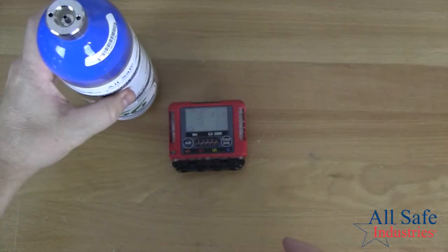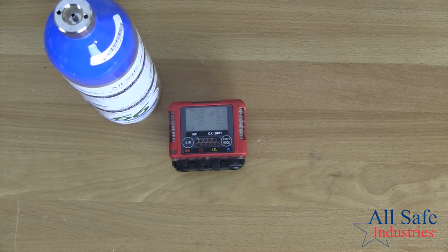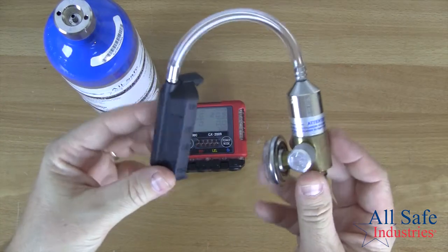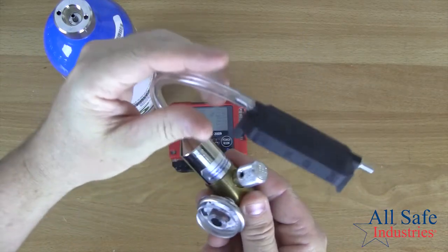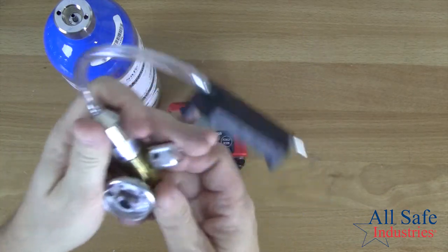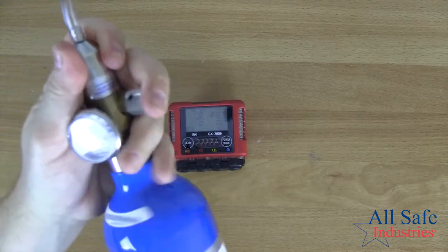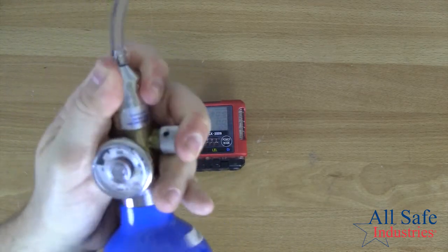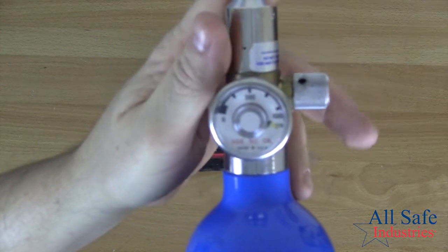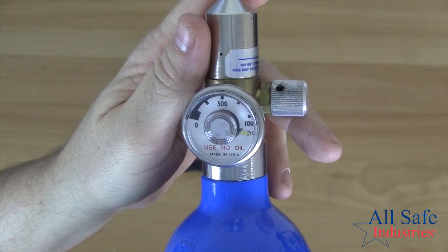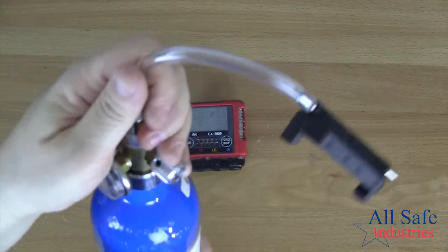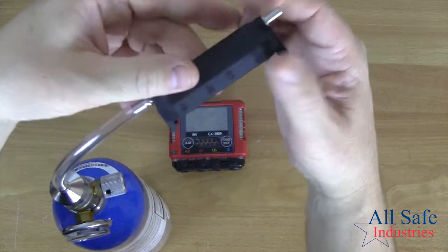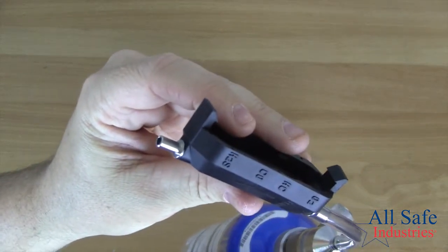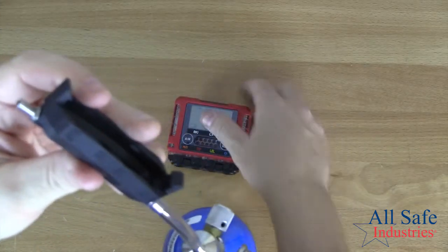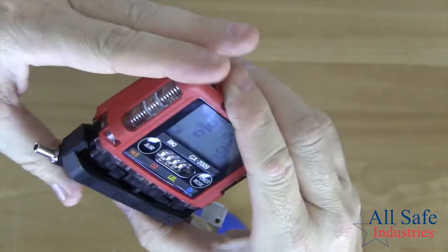So we've got the cylinder of calibration gas. You're also going to need the regulator and the calibration cup so that we can apply the gas right to the sensors. So we're going to engage the regulator onto the cylinder. You'll want to check the gauge, see that the gauge goes up and shows pressure in the cylinder. That tells me that we do have gas in there. We've already checked our expiration date. And then when you install the instrument into the calibration cup, there are the names of the gases right on the side of the cup. If you can see those names of the gases, we want to line our meter up to match that. It's just the way the factory recommends it.